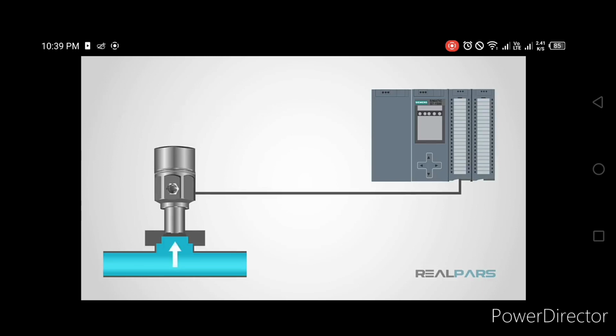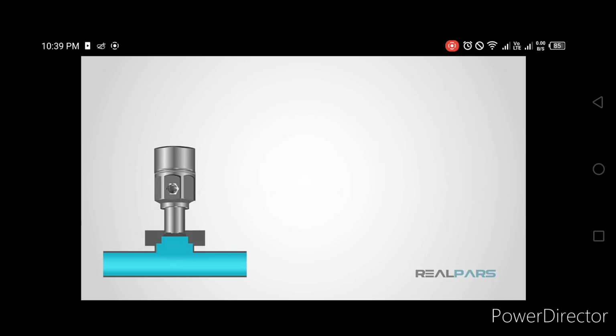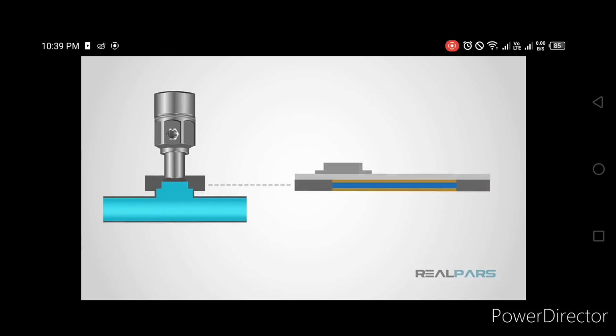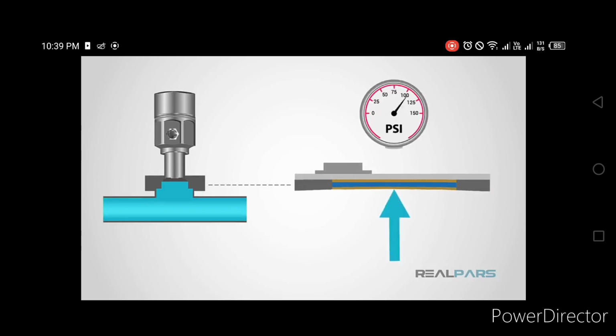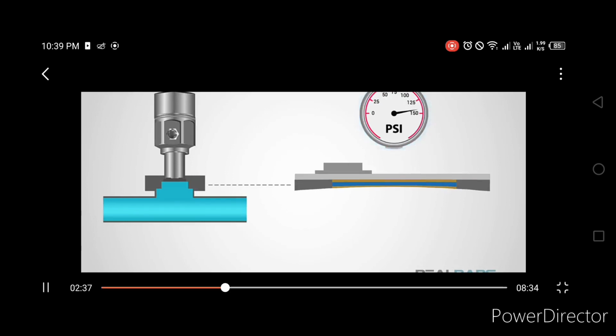Two common signals that are used are a 4 to 20 milliamp signal and a 0 to 5 volt signal. Most pressure sensors work off of the piezoelectric effect. This is when a material creates an electric charge in response to stress. The stress is usually pressure, but can be twisting, bending, or vibrations. The pressure sensor detects the pressure and can determine the amount of pressure by measuring the electric charge.